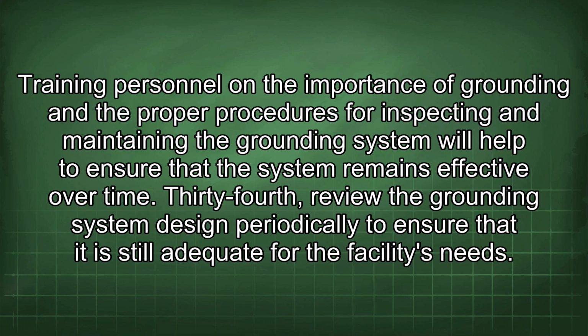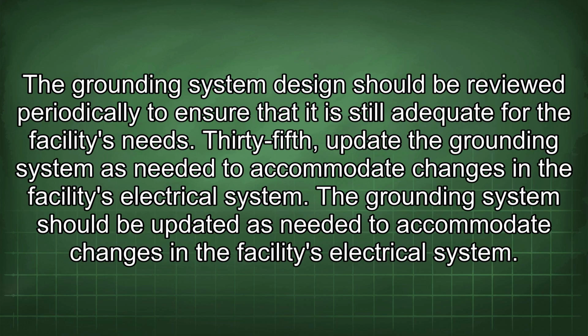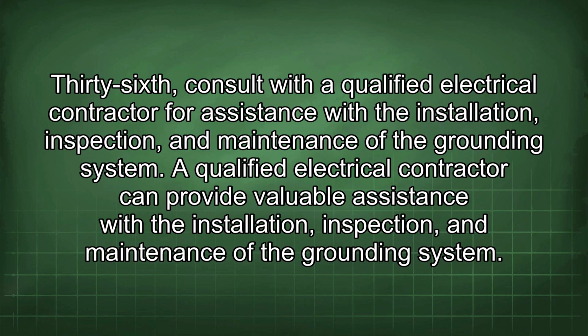34th, review the grounding system design periodically to ensure that it is still adequate for the facility's needs. The grounding system design should be reviewed periodically to ensure that it is still adequate for the facility's needs. 35th, update the grounding system as needed to accommodate changes in the facility's electrical system. The grounding system should be updated as needed to accommodate changes in the facility's electrical system. 36th, consult with a qualified electrical contractor for assistance with the installation, inspection, and maintenance of the grounding system. A qualified electrical contractor can provide valuable assistance with the installation, inspection, and maintenance of the grounding system.